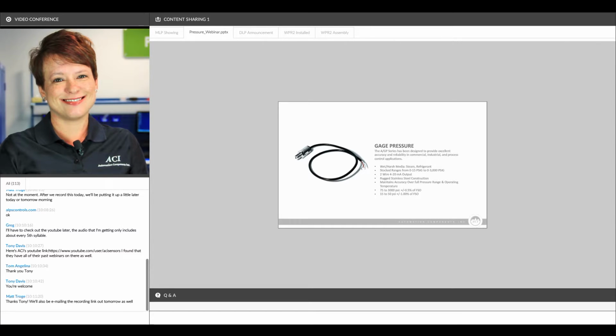The unique thing about this device is it's guaranteed to hold its accuracy not only over the full calibrated pressure range, but also over the full compensated temperature range. And there's a couple different accuracies available depending on which pressure range you're using. The lower pressures are going to have accuracies of plus or minus 1% of full-scale output. Higher pressures are going to be plus or minus 0.5% of full scale. And you can kind of see those spelled out for you there on the slide if you wanted a little more information.